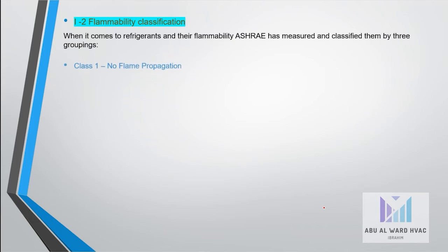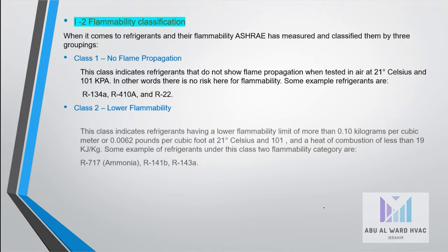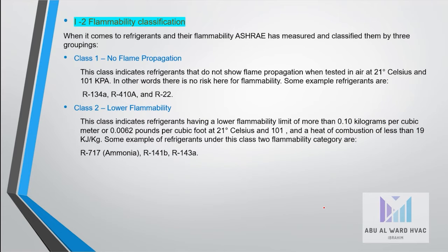The second classification is flammability, according to ASHRAE. Class 1 is non-flame propagation: this class indicates refrigerants that do not show flame propagation when tested in air at 21°C and 101 kPa, such as R22. Class 2 indicates lower flammability, such as R717.